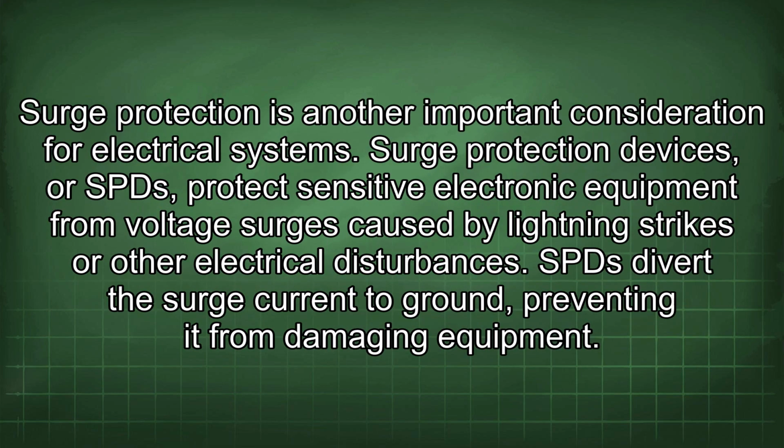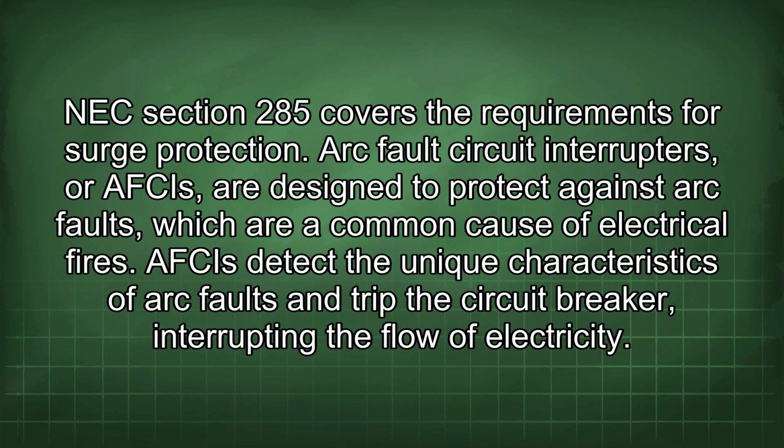Surge protection is another important consideration for electrical systems. Surge protection devices, or SPDs, protect sensitive electronic equipment from voltage surges caused by lightning strikes or other electrical disturbances. SPDs divert the surge current to ground, preventing it from damaging equipment. NEC Section 285 covers the requirements for surge protection.